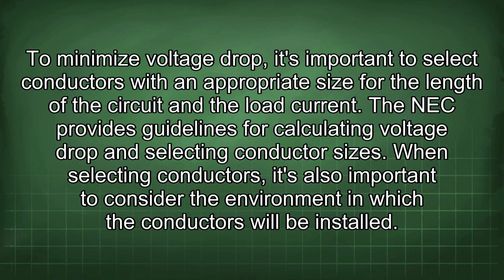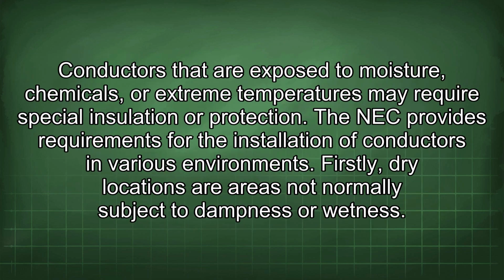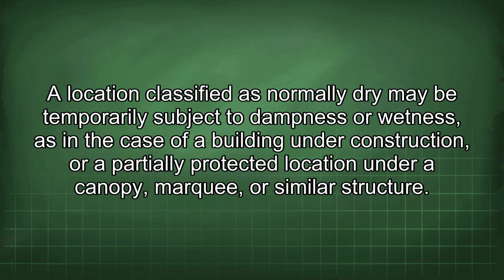When selecting conductors, it's also important to consider the environment in which the conductors will be installed. Conductors that are exposed to moisture, chemicals, or extreme temperatures may require special insulation or protection. The NEC provides requirements for the installation of conductors in various environments. Firstly, dry locations are areas not normally subject to dampness or wetness. A location classified as normally dry may be temporarily subject to dampness or wetness, as in the case of a building under construction or a partially protected location under a canopy, marquee, or similar structure.